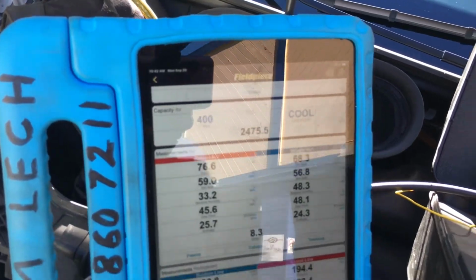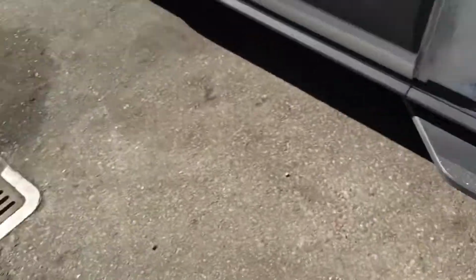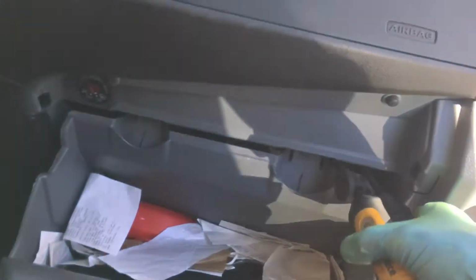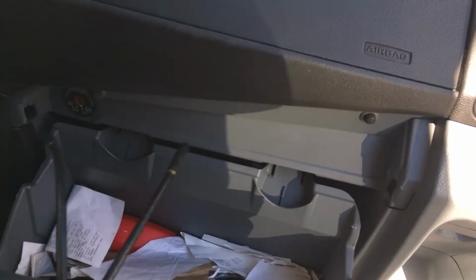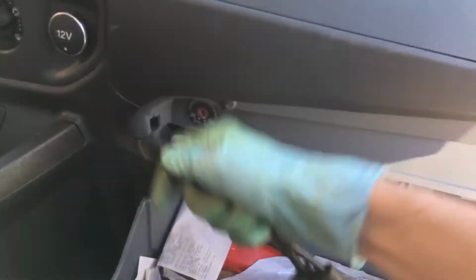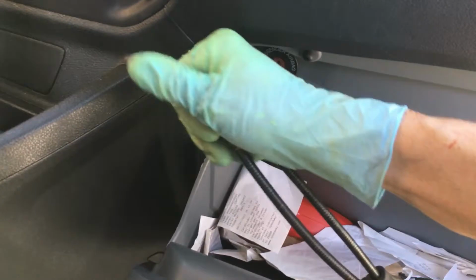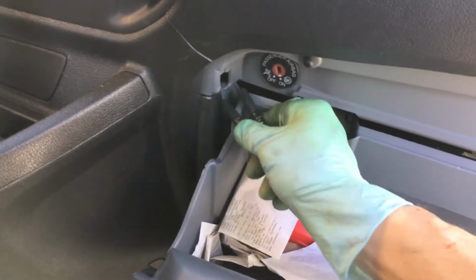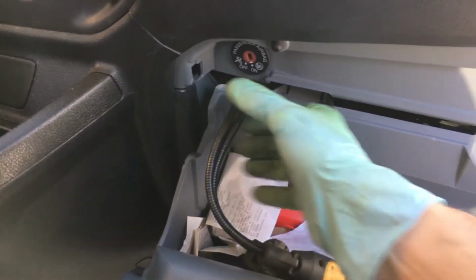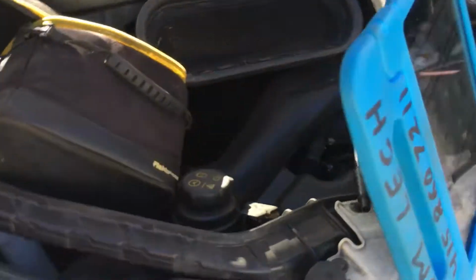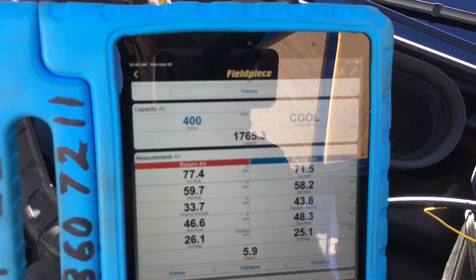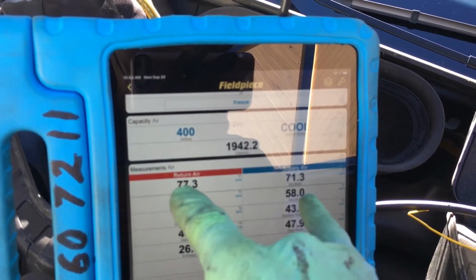Now, because I have the probe stuck in and they're a few inches apart from each other, 7 degrees is not kosher. So there must be a little bit of air bleed out from something hot. Let's get these right next to each other so I can confirm. I don't want any deviance. I don't want anything skewing my readings. I have like a 7 degree difference. Right here, I could literally feel air moving across me because there's a breeze. I should not be having a 6 degree difference. Did I just cook my temperature probe?